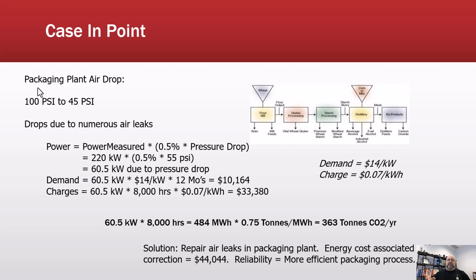So if I have a 100 psi system and at the end of that compressed air line I only have 45 psi, that difference of 55 psi is air leaks. So if I have numerous air leaks, and not all of them are audible, I would take a power measurement.